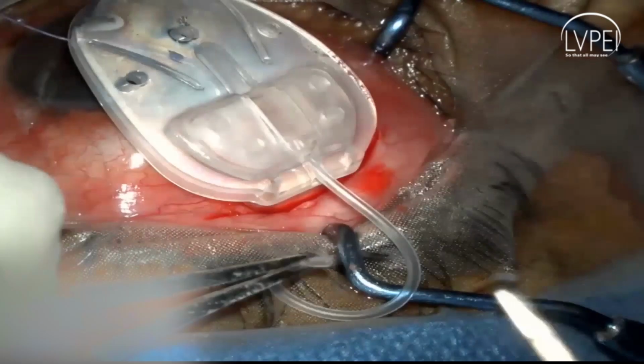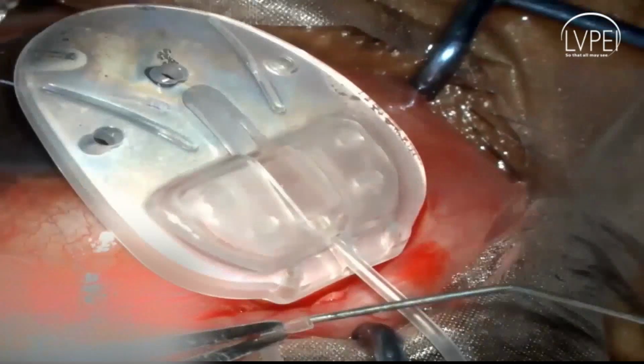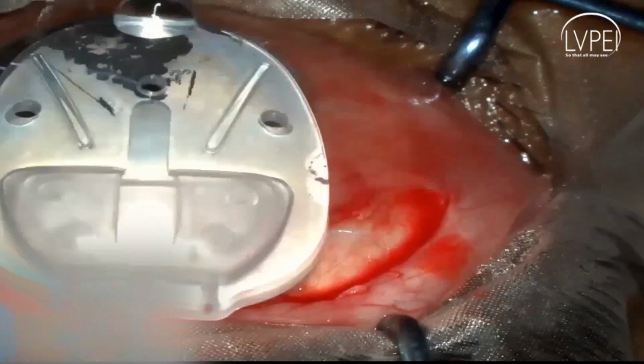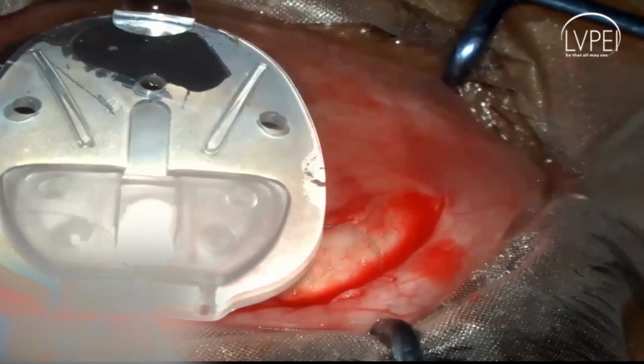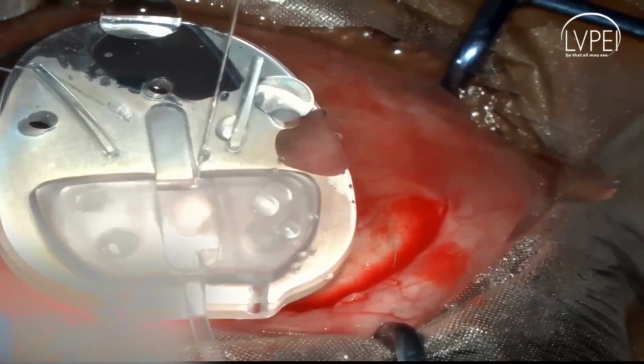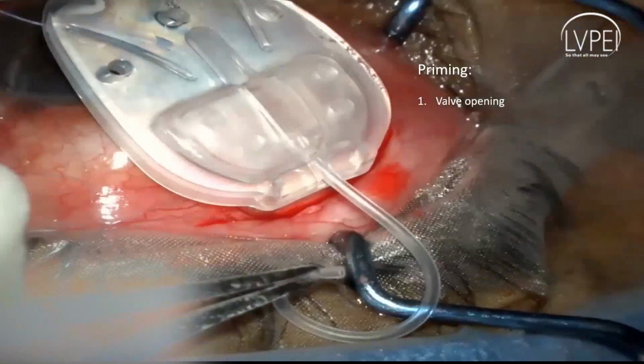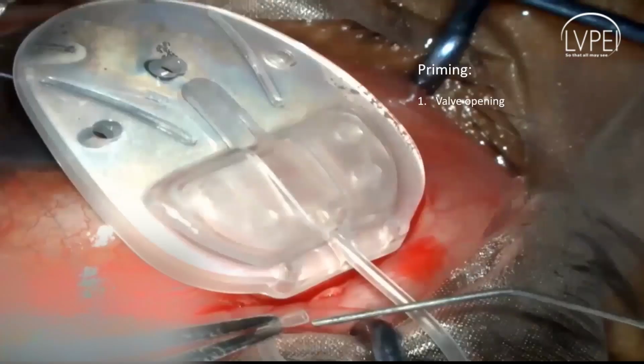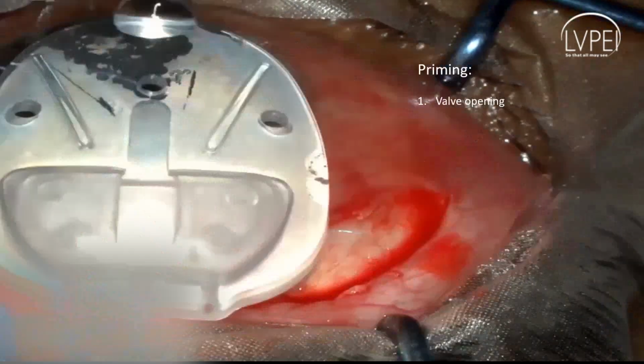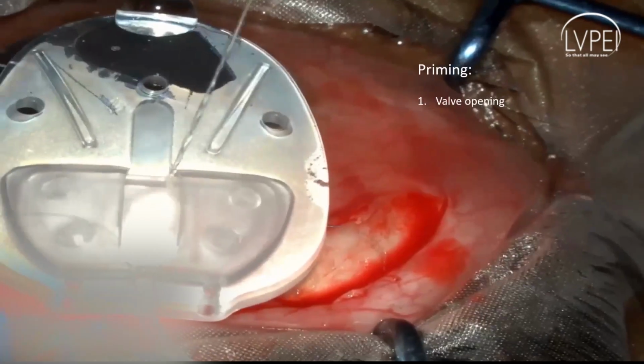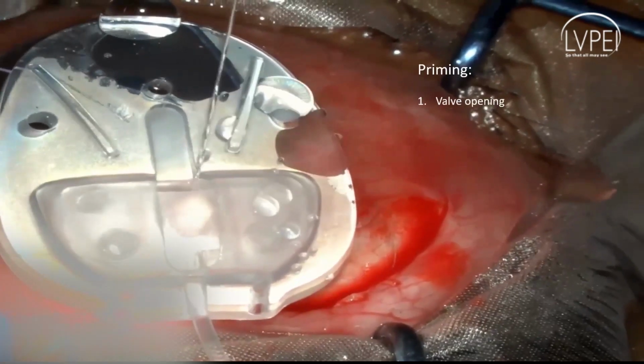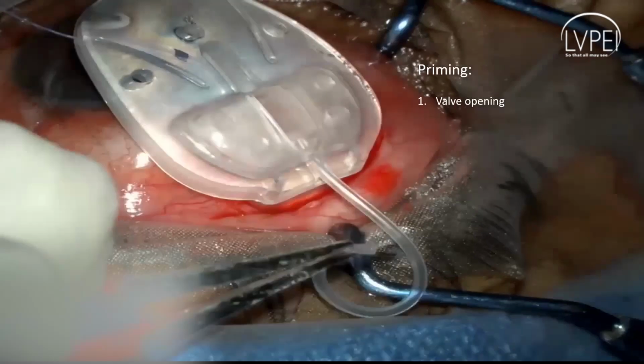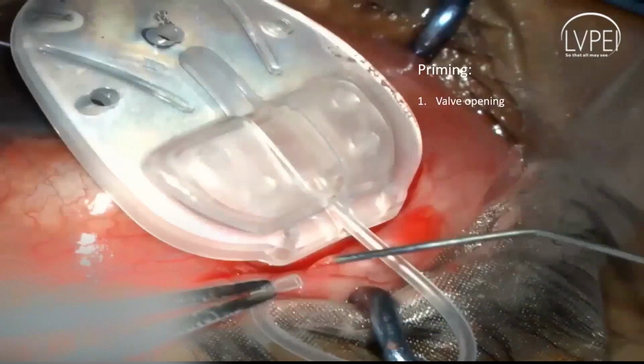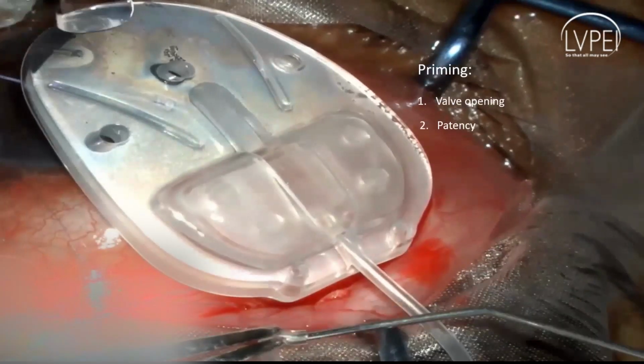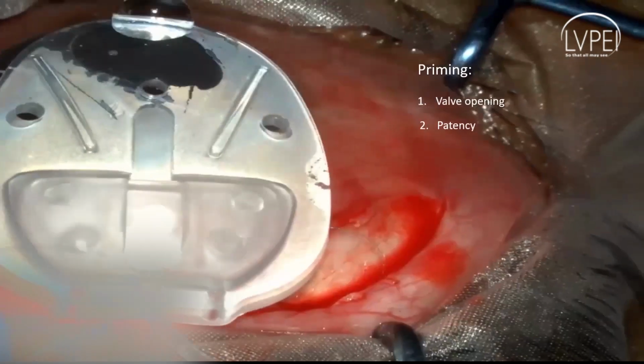Priming the implant, especially under microscopic observation with a 5 cc syringe using a 27 gauge cannula, primarily separates the two leaflets and creates a space for the smooth outflow of fluid from the tube at the valve outlet for the regulatory flow of aqueous. While secondarily, the patency of the tubes is checked while priming.